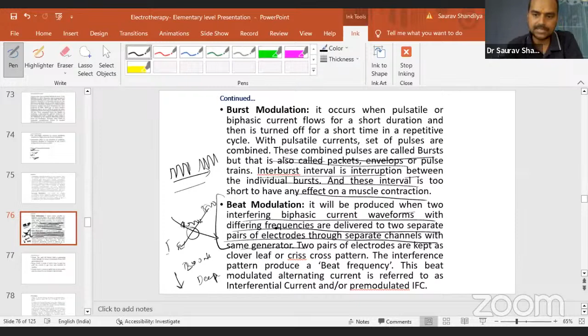Beat modulation is produced when two interfering biphasic current waveforms with differing frequencies are delivered to two separate pairs of electrodes through separate channels from the same generator. You know IFT: one medium frequency current is coming at 4000 hertz and another at 3800 hertz. The difference will be 200 hertz, and the lower frequency will have more intensity, going deeper into the tissue. This is how, on the basic concept of beat frequency, IFT works.